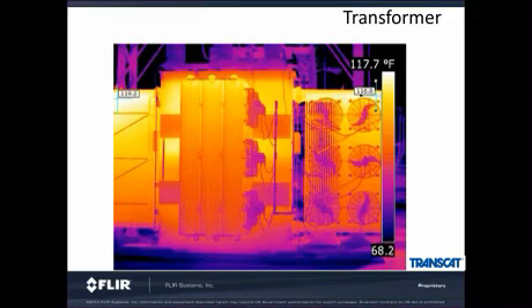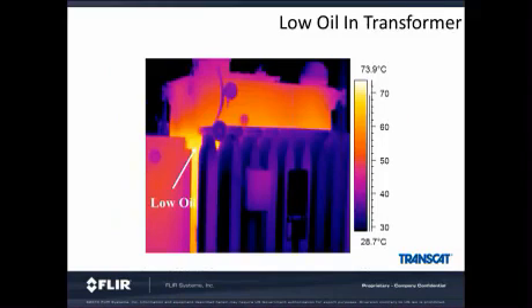Here's a picture of another transformer. The left side is about 3 degrees warmer than the right side. The left side measures at about 119 degrees, with the right side measuring about 116 degrees. There is only a 3-degree rise, but over time this could get worse. Excessive heat will reduce the life cycle of a transformer, so discovering this issue will allow the utility to repair it when possible. In this case, the transformer had shifted, the pad had sunk on one side, allowing the oil to move to the other side and thereby reducing some of the oil flow in the high side.